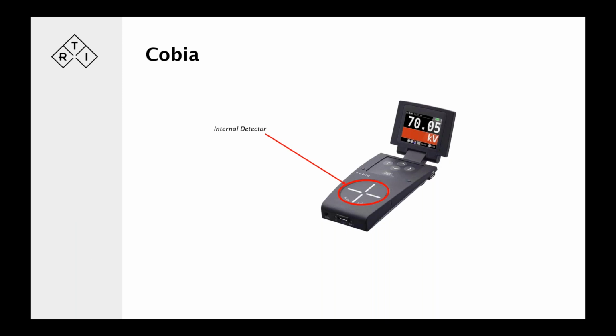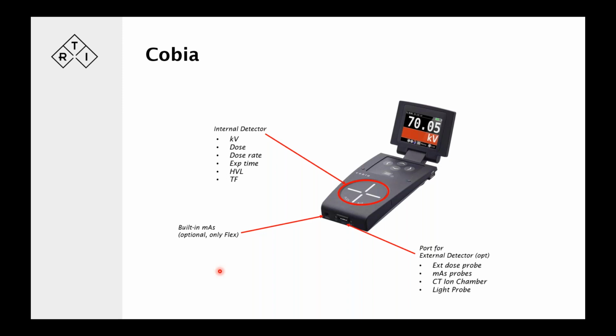So the detector is built in with the crosshairs on it, and that also gives you kV, dose rate, exposure time, HVL, and total filtration, as does the Piranha. So it's a basic tool for X-ray testing, like any other tool on the market. What it does have also is a built-in mAs function. If you can make out a small plug-in here, that's a 3.5 millimeter socket for the built-in mAs. Then we have a port for external detectors. Some versions of the Cobia have it, some don't, it's optional. That's where we can fit the external dose probe, mAs probes, CT ion chamber, light probe, and CT dose profiler, and get similar measurements as we do out of the Piranha. So it can be quite a flexible instrument in this way.